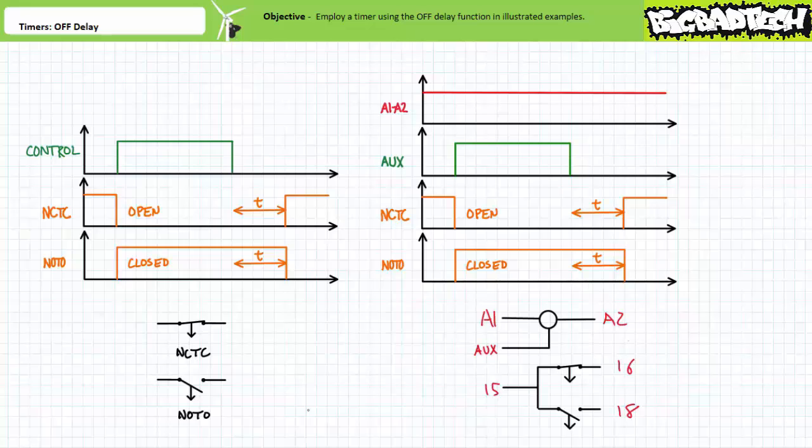Note, for the purposes of this general lecture, I'm trying to avoid getting entangled in manufacturer specifics. It is your responsibility to interpret the timing diagram for your particular multifunction timer of interest. Note if a timer necessitating an auxiliary controlling input executing the off-delay function lost power to the coil during the off-delay period, the associated contacts would halt the delay, immediately return to their deactivated state, and reset the timer. This allows an off-delay timer conducting the delay to be overridden by an emergency input for immediate stop purposes. We'll examine this feature in a moment.